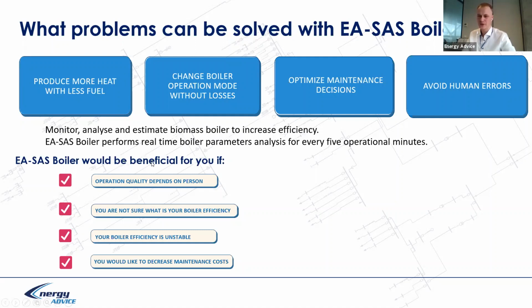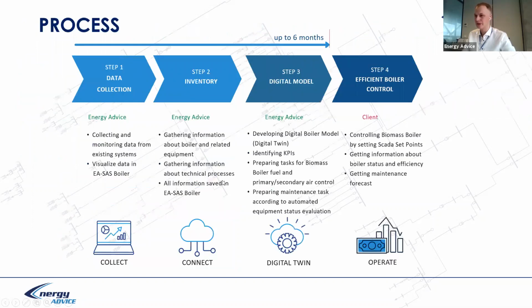Why would a digital twin with ISS boiler be beneficial for you? Because operation quality depends on the person, or you are not happy with boiler efficiency because of your control system operation. Your boiler efficiency is unstable. Later I will show some real examples with efficiency dependence on the amount of heat produced, and you would like to decrease maintenance costs. So if this is true, you would benefit from this solution.